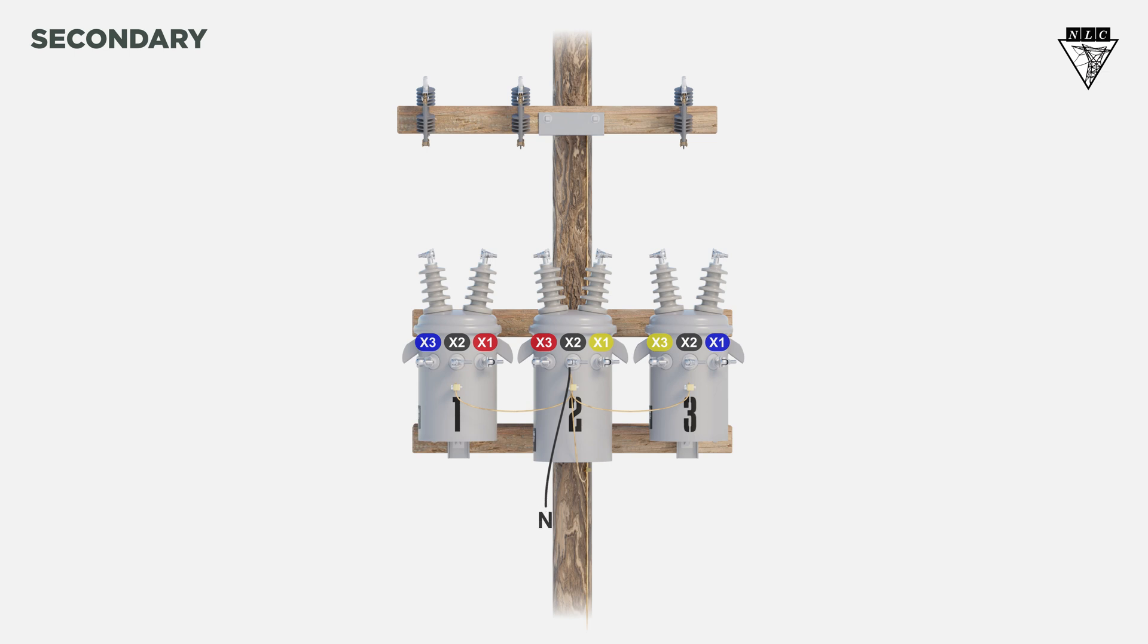Connect the X3 of the second transformer to the X1 of the first transformer. Connect the X1 of the second transformer to the X3 of the third transformer. Then, connect the X1 of the third transformer to the X3 of the first transformer.